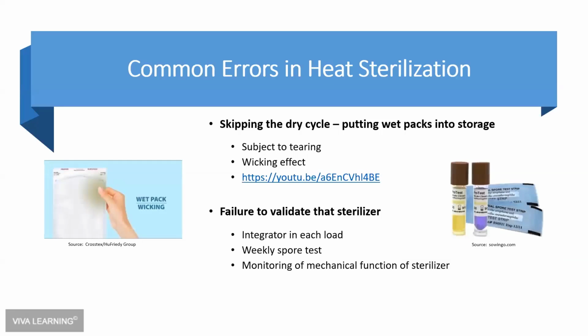So let's talk about some of the errors we have in heat sterilization. This one has to do with packaging, and it's probably one of the most common ones that I see as a consultant. Skipping the dry cycle, taking instruments out when they're wet, there's still condensation inside the packages. That makes them subject to tearing, and subject to what's called a wicking effect. If you look at the picture on the left-hand side, you can see that if I touch this package with contaminated hands, I can actually wick microorganisms into that package if the material is wet.